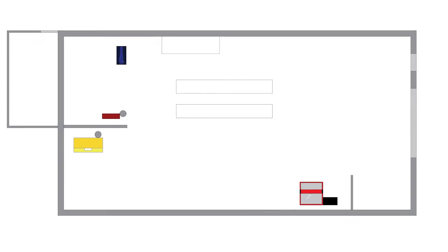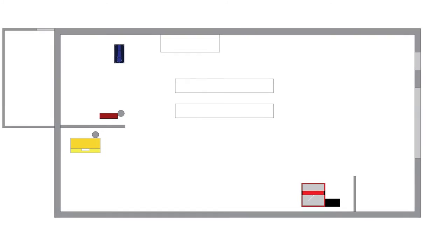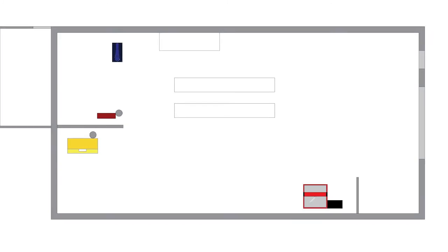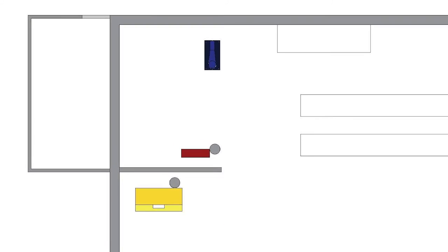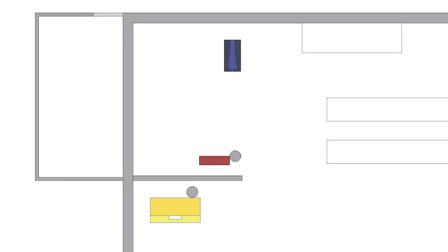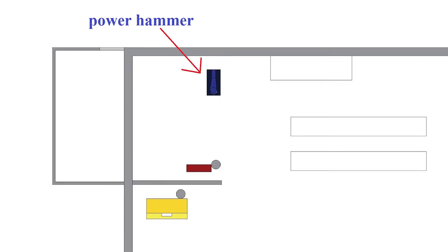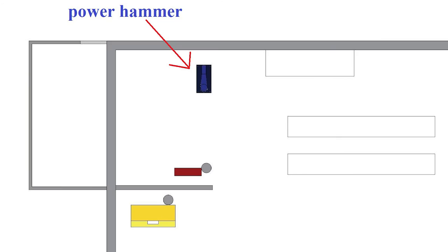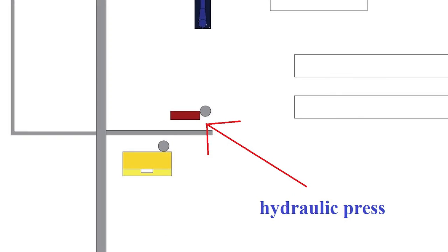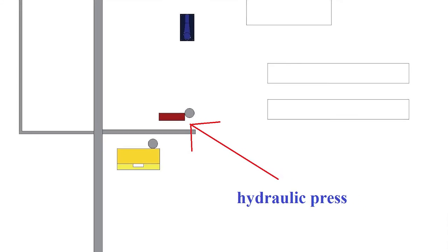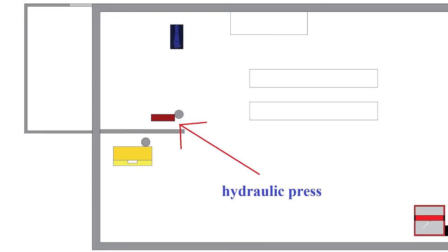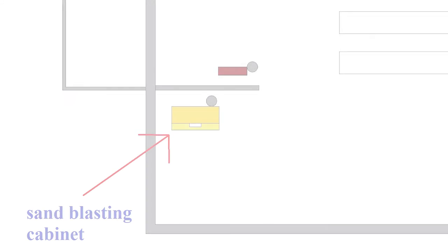Next, we want to look at the loads on the shop that we will put on the air system and where they are placed. The forging area in this shop will go on the other side of the wall from the compressors. This will put the power hammer that uses 21 CFM of free air at 140 PSI and the air over hydraulic press that uses 40 CFM of free air at 120 PSI as close to the compressors as possible.